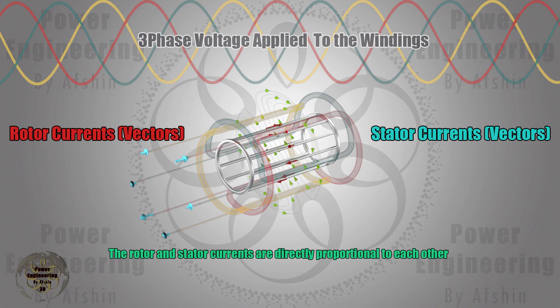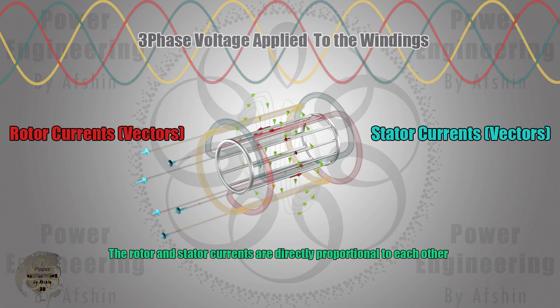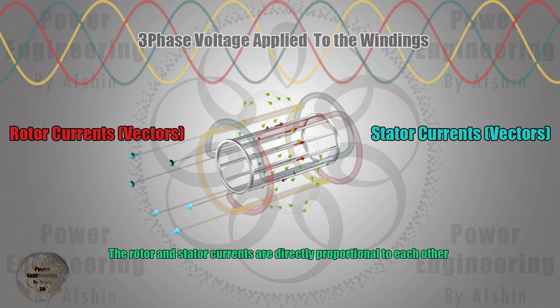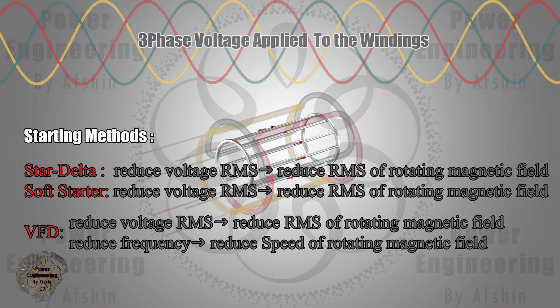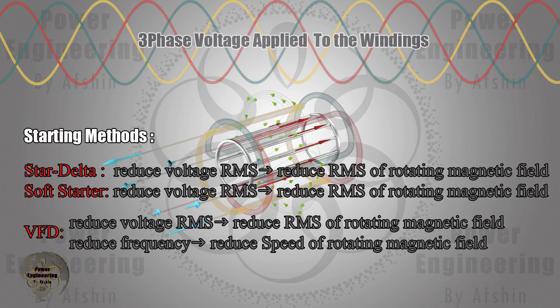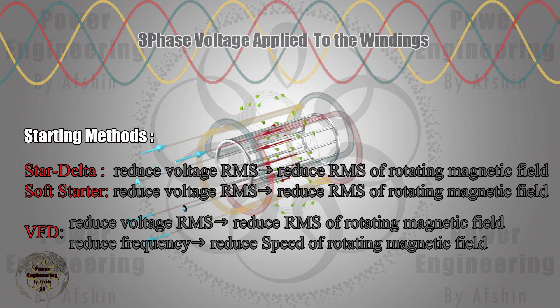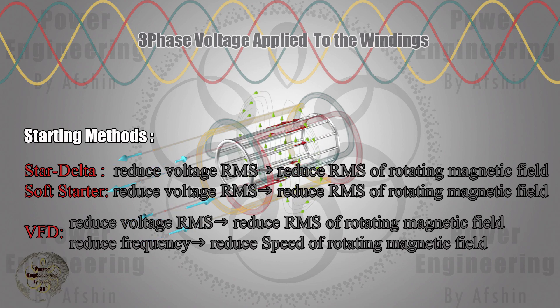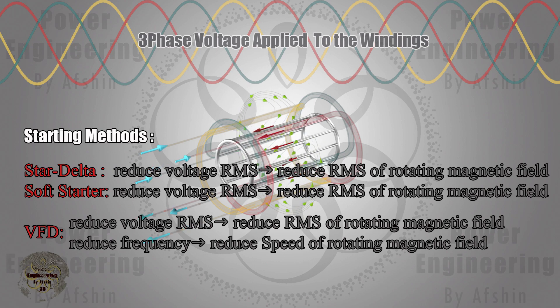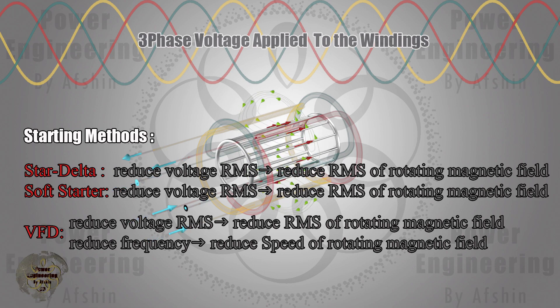Finally, let's examine why starting methods like star delta, soft starters, and VFDs reduce starting current. Starting current depends on two factors: flux magnitude and the rate of flux change. Flux magnitude can be adjusted by controlling the input voltage and the rate of flux change by controlling the source frequency.